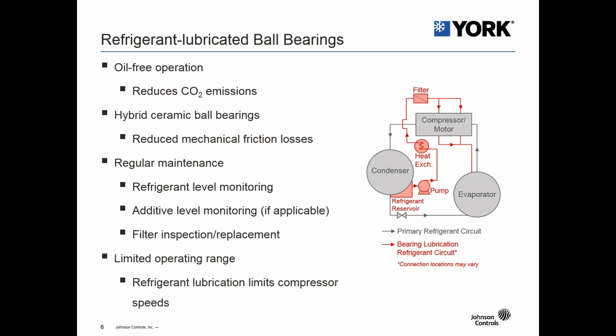A heat exchanger is still required to make sure that there's precise control of the refrigerant operating temperature prior to it going to the bearings, and it still requires a filter. So there really isn't a difference from a chiller package layout other than there's no oil in the system. So this system still requires regular maintenance.